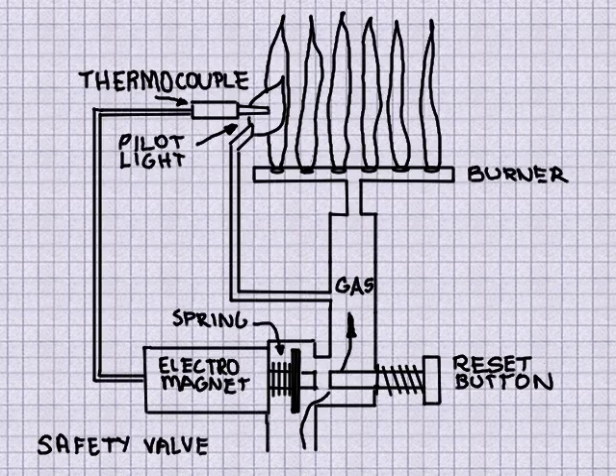Gas safety valves are designed to turn off a burner if the pilot light goes out. The thermocouple hot junction is placed in the flame and provides enough current to power an electromagnet which holds the valve open. And that is kind of amazing, since you will not need a complicated circuit powered by batteries or any other external supply.